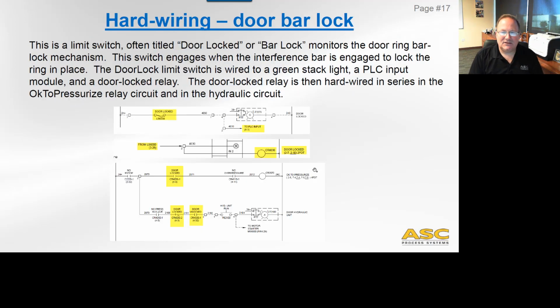And a very important one is the door bar lock. This is a limit switch often titled door locked or bar lock, monitors the door ring bar lock mechanism. This switch that's shown right here is usually tied to a green light, usually one of the stack lights, or it could just be a door locked light, and to a PLC input, and to a relay called door locked. Okay, and that relay then is used in the OK to pressurize relay, which again is a permissive for auto enable, so we can say that the door needs to be locked for both pressure and for heating to occur, and it's also used to interlock the hydraulic operations of the autoclave so that the door is not locked when the hydraulics are to be run.